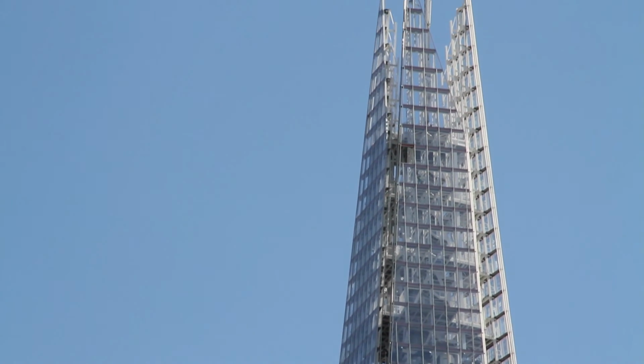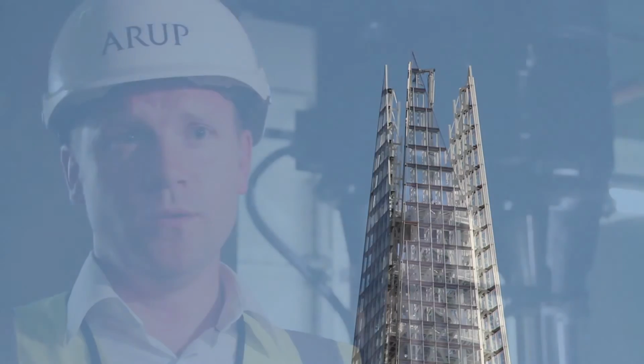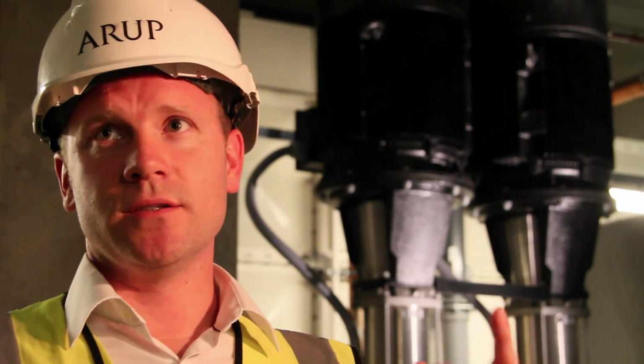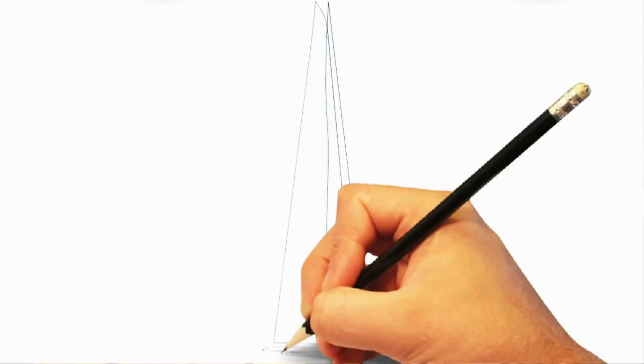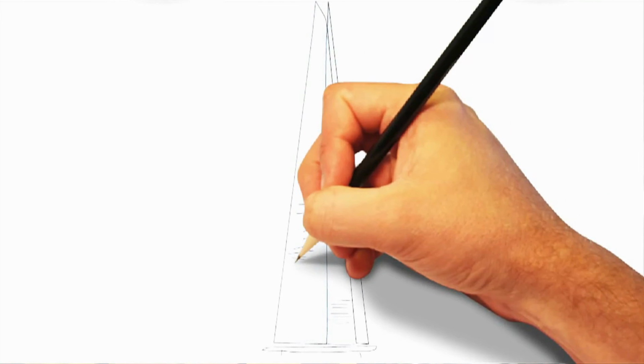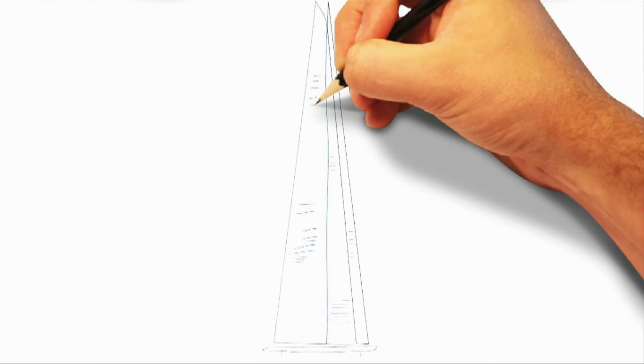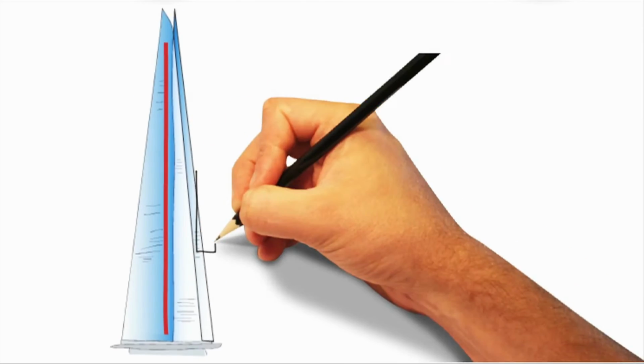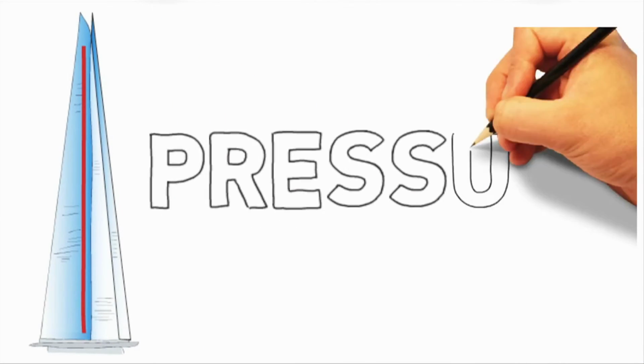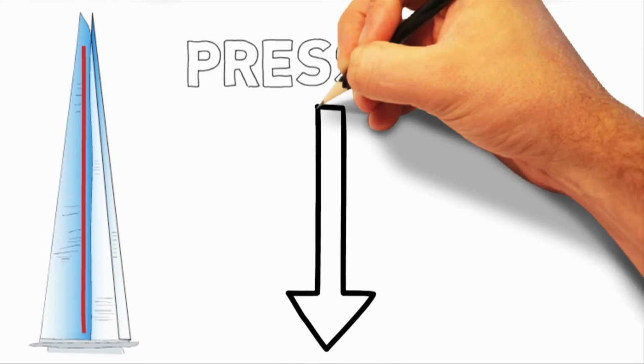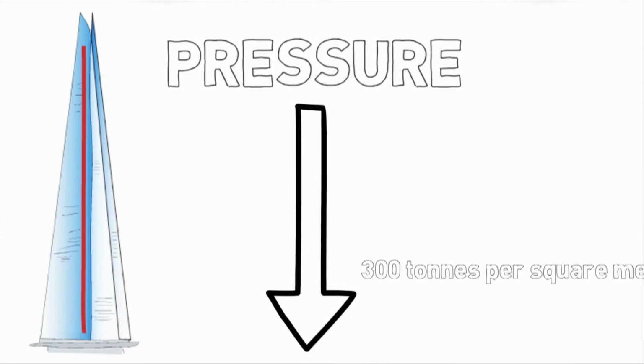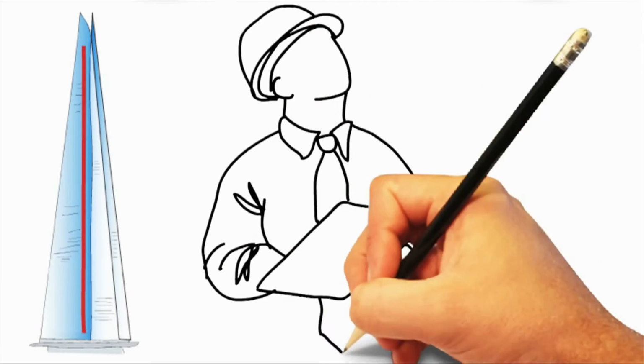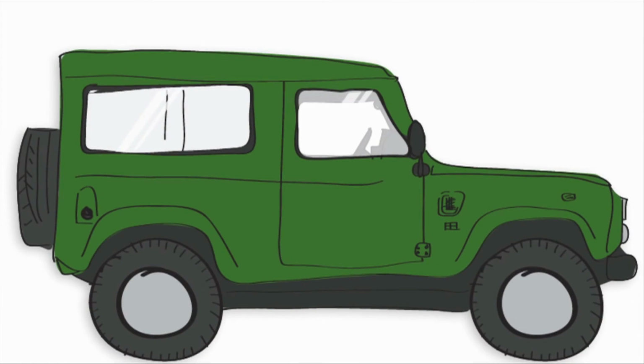So why have we put all these pumps and tanks in this building? Why not pump it directly from the basement here all the way to the top of the Shard in one go? The answer is pressure. If a column of water stands in a single pipe from the top of this building to the bottom, due to the weight of the water, the pipe at the bottom must withstand a pressure of 300 tons per square metre. That's the equivalent of me trying to hold a 4x4 in the palm of my hand.